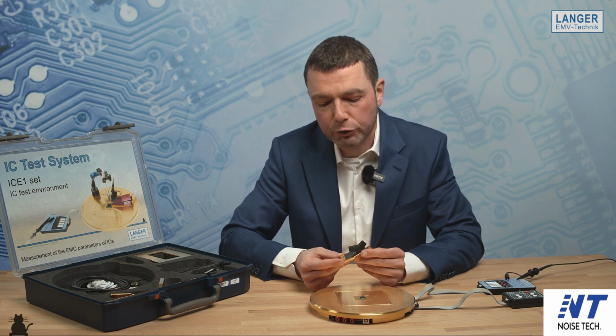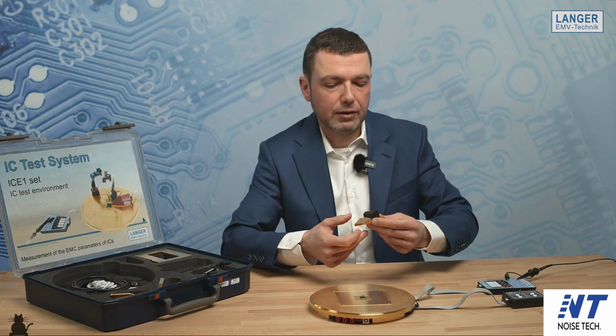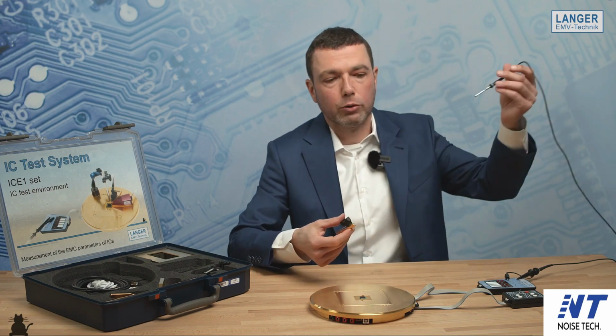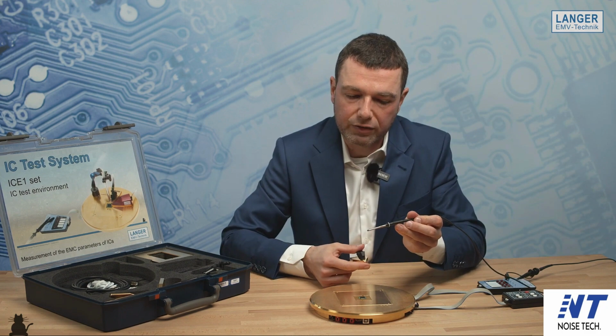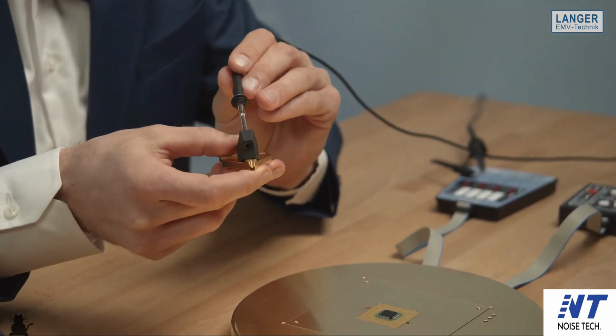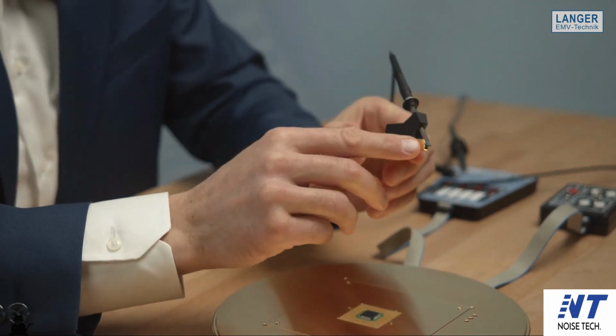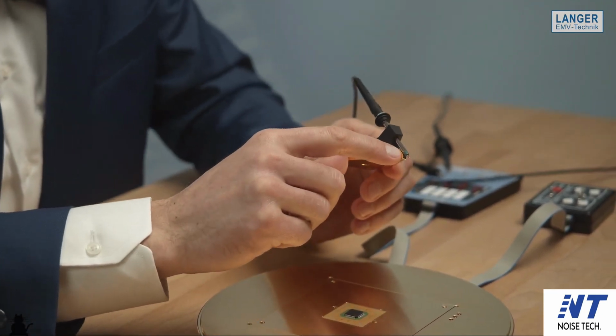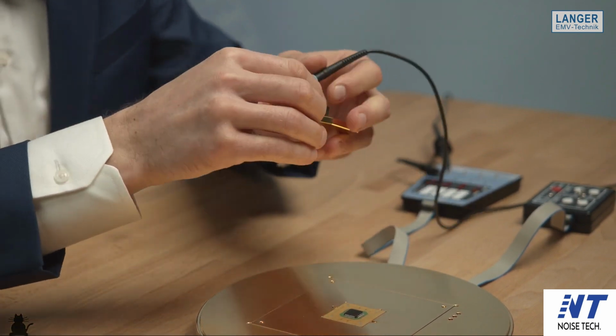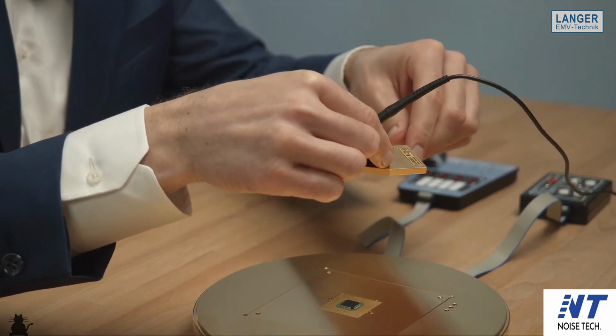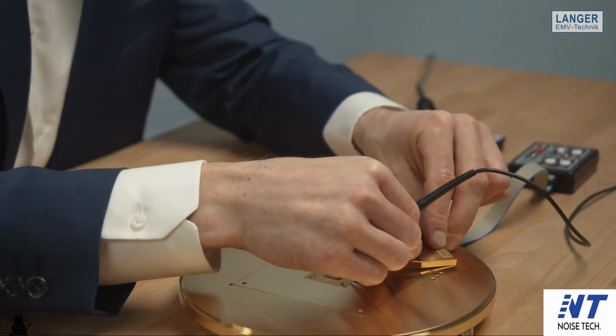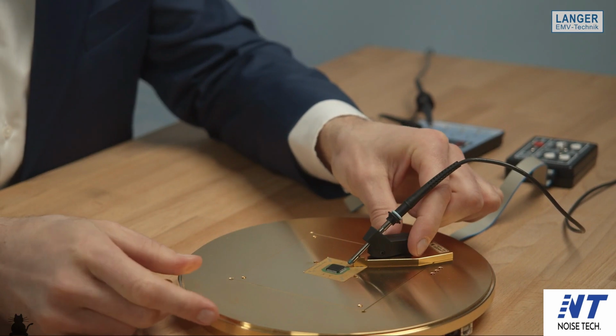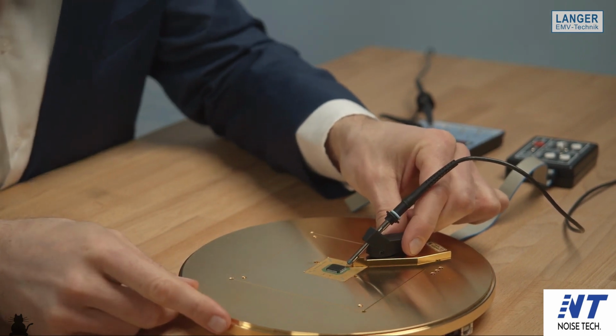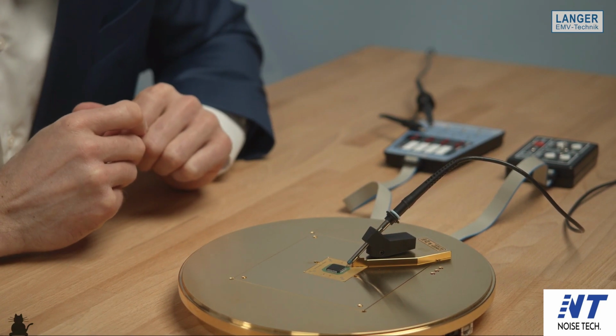If you want to measure high-speed signals in the frequency range of 100 MHz, you can use this probe holder here. With this holder, you can also use a probe of an oscilloscope and bring it directly into the holder, where you have a very good and short ground connection in front of this holder. With this magnetic holder, you can adapt and adjust it very easily on this ground plane and bring it directly to an IC pin for the measurement.